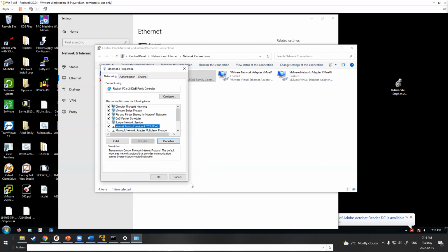So if you accidentally made your computer the main PLC or the main drive or the safety controller or the server, the historian server, the data uplink server, the main router, something that everything needs to talk to, all of the communications, the switches could then start trying to forward your machine data, and then everything could fault if their comms die.